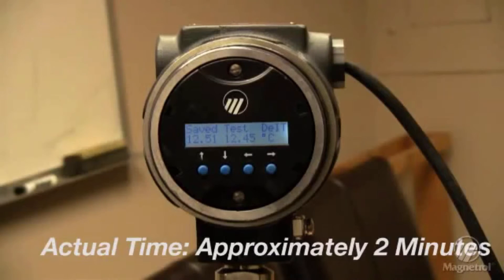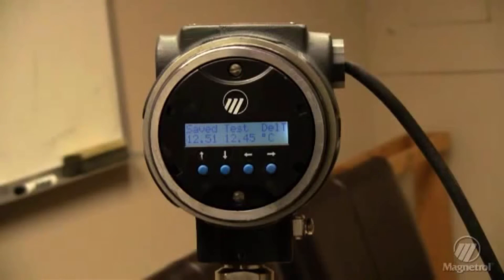One is the original temperature difference between the sensors as it left the factory and the other is the new temperature difference measured. If the values are within 1.5 degrees, the unit is still within calibration.